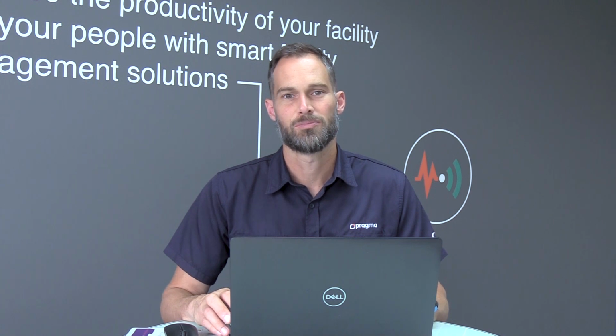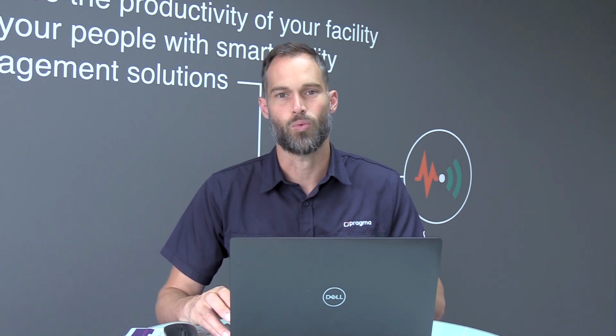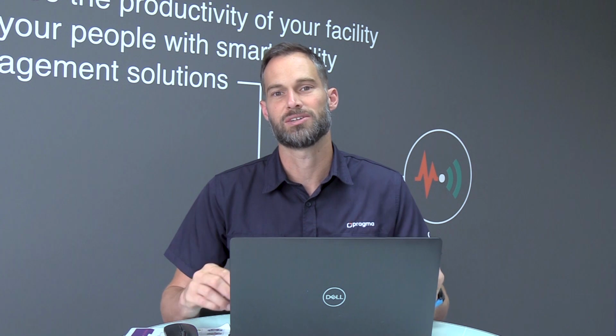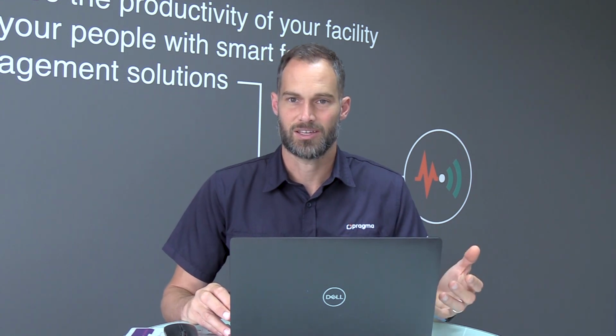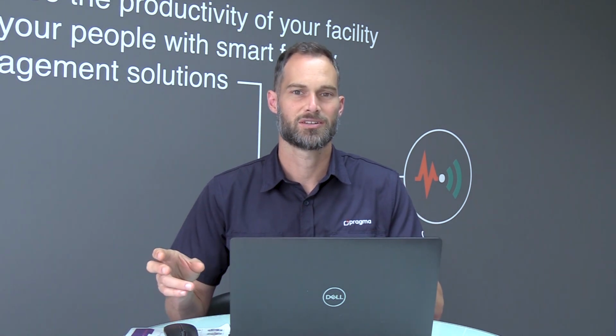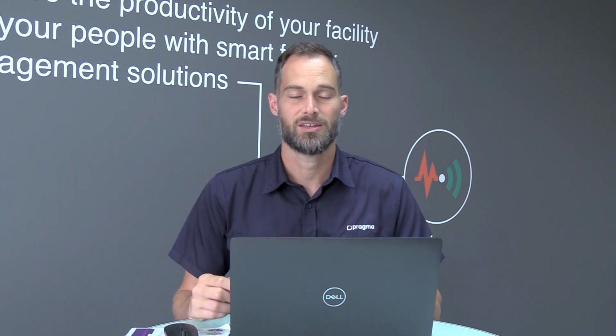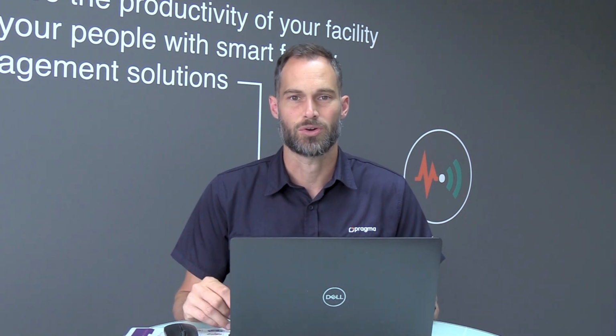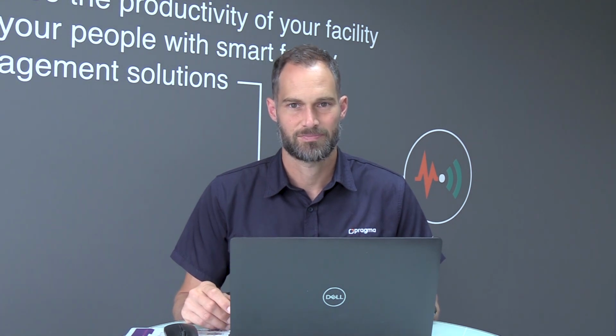So what we're going to do is set up an option within OnKey that allows us to put in the rating value in the asset tree. Now this rating value, based on our example, is either 100 kVA or 200 kVA. And then there's a rule also attached to two different tasks stating that if it's a 100 kVA generator, then use the change oil 100 kVA task. If it's a 200 kVA generator, then make use of the change oil 200 kVA task. Alright, let's go to OnKey and have a look at what we can do there.